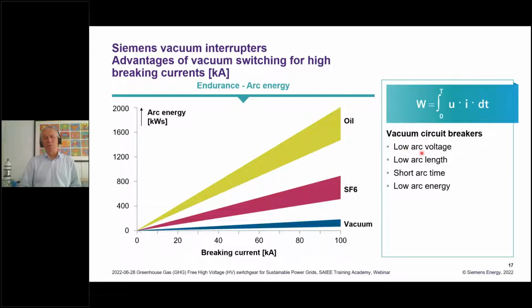That has 4 reasons. There is a low arc voltage, there is a low arc length, there is a very short arc time, and overall you get a very low energy. What does it mean if you have low energy in? You have low wear, so the contact systems are not as stressed as an SF6 one or oil one, and you need less energy to switch. And needing less energy, the whole system is less stressed. So that's the reason why the vacuum interrupter is so strong, and why the vacuum interrupter in medium voltage is the clear leading technology, and for high voltage will become the leading technology.